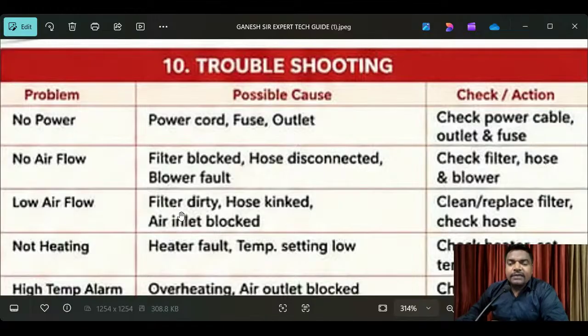Yes. Now come here. Filter dirty, hose kinked, air inlet blocked. Troubleshooting: problem, cause, then check action. What to do as a biomedical engineer? Clean or replace the filter and check the hose. Okay, these are very simple things you have to focus on, because sometimes, if you diagnose and find out the issue very clearly, then we can resolve the issues without replacing any major spare parts. That is the major trick of biomedical engineering. That is the reason I'm going to give you all this information.